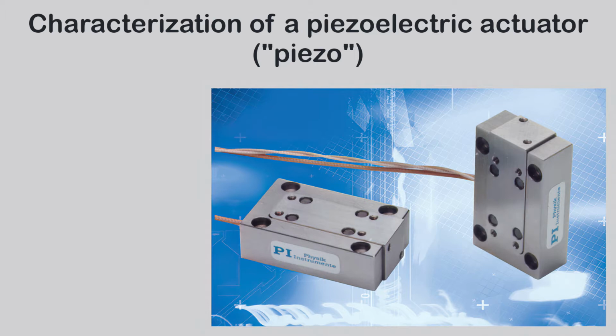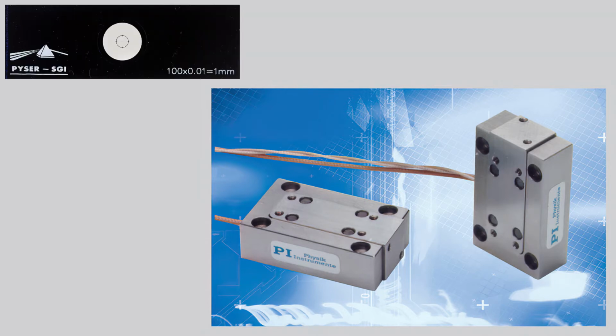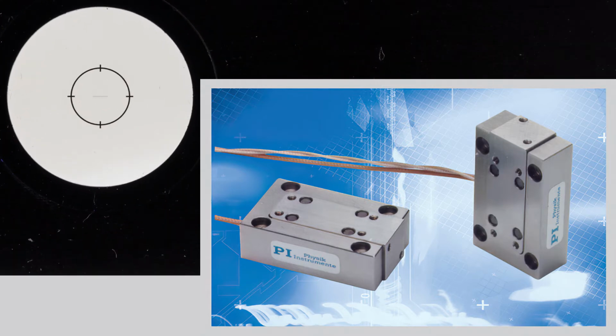We will use an upright reflected light microscope and visualize the piezo motion with the help of our familiar microscale. We simply put the scale onto the moving part of the piezo, where we can hold it in place with a small magnet. The reflected light image of the microscale looks like this.